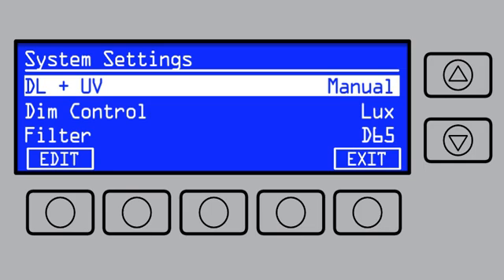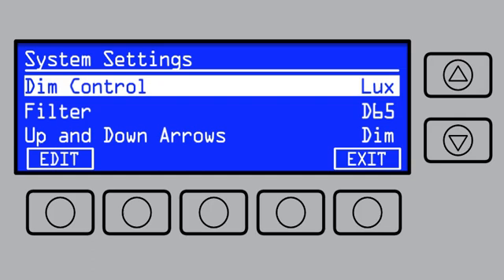The factory default automatically uses UV. You can use DL plus UV to change this to manual. Dim control allows you to set fluorescent lamp dim control by lux or by voltage. UV is always dimmed by voltage.